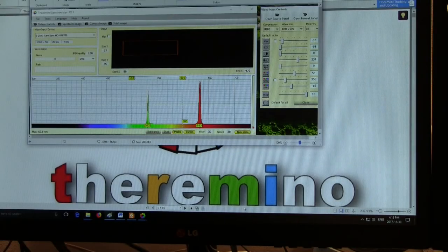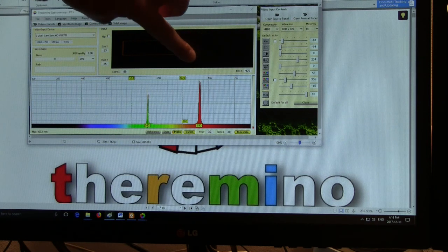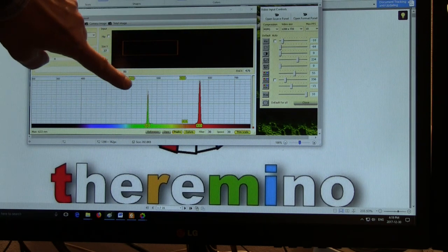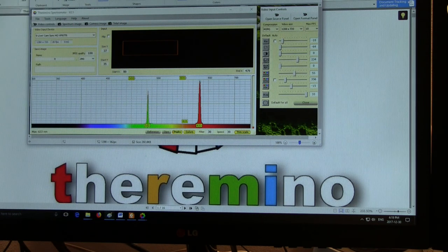Another spectrum that was quite interesting was this one that we developed with the visible spectrometer. And this is looking at two lasers. One is a 632.8 nanometer helium-neon laser, and the other one is a 532 nanometer green laser. And I've shone them both on the spectral slit at the same time, and we got this very nice pattern here that is quite useful for calibrating, because you know what the wavelengths of your lasers are, so you can line them up with your system and see them quite clearly. So that was quite good.